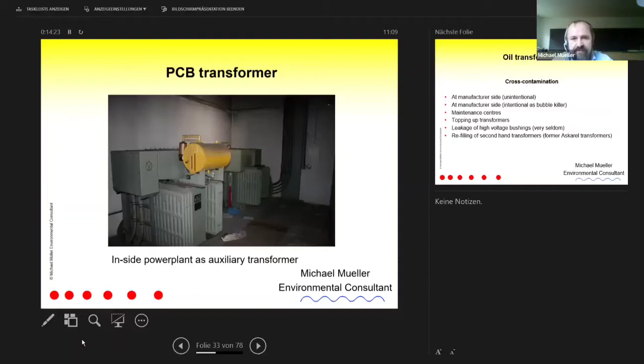Okay, oil transformers, we have the cross contamination. That could be at manufacturer sites, unintentional. How? Well, if you know how the transformers are produced, the core is built, and the coil goes to the dry oven. The coil is dried so that the water gets out, because water is toxic for the transformer. Then it comes out, it is put in the casing, closed, and the transformer goes to the filling station. It is the same transformer, it could be filled with Askarel or with oil. It's just the request of the customer who said, I want to have an Askarel transformer because it's a fire risky place, as an example.